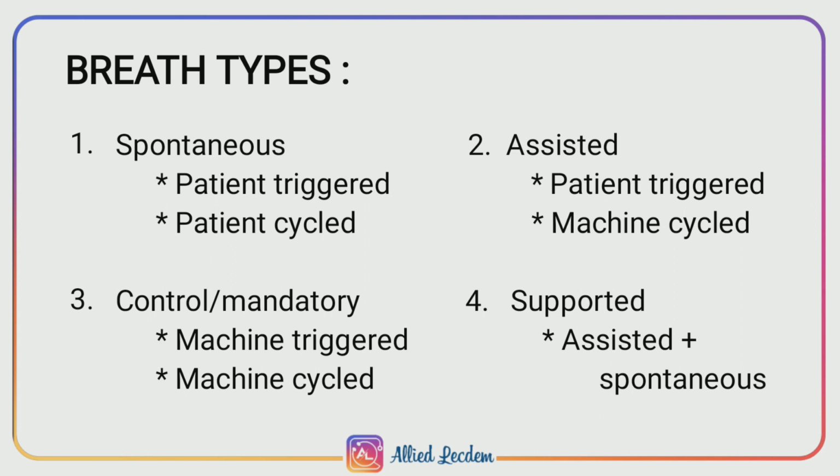Third, control or mandatory. In this mode, the total breathing of a patient is controlled by the ventilator at a preset tidal volume and respiratory rate. Shortly, you can say that there is no spontaneous effort by the patient. It is machine triggered and machine cycled. Fourth, supported. Here, the patient will breathe on his own, which is spontaneous breath, and the ventilator will be assisting or supporting the patient in doing so.